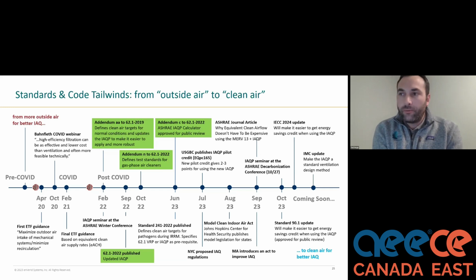So in February of 2022, Addendum AA to ASHRAE 62.1 2019 was brought in, which gave us defined clean air targets to hit, specifically with gaseous contaminants. All right. Addendum N to 62.1 2022, which came out in October of 2022, also gave us a levelized playing field, where Addendum N really states, how do I know a device is working sufficiently to reduce outside air? And one of the interesting things there is really using devices that don't produce byproducts.